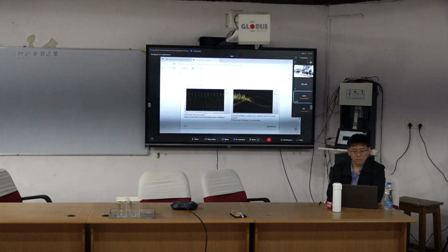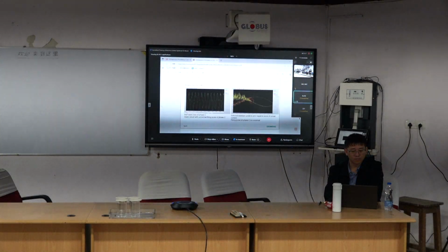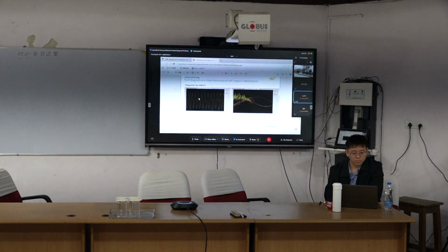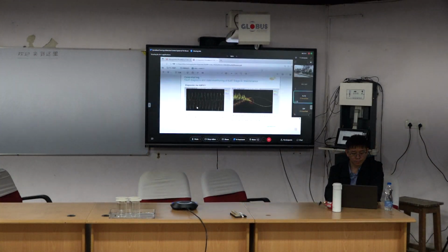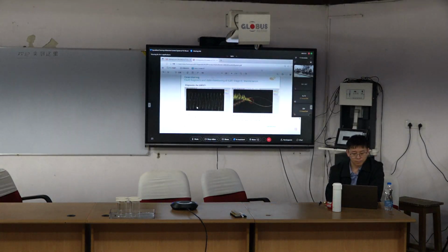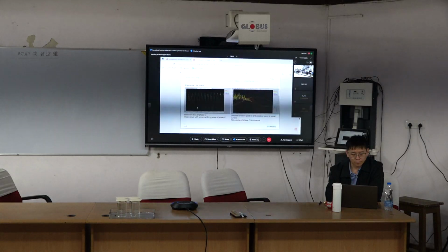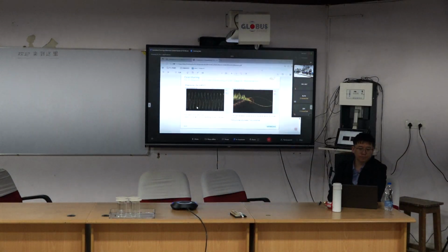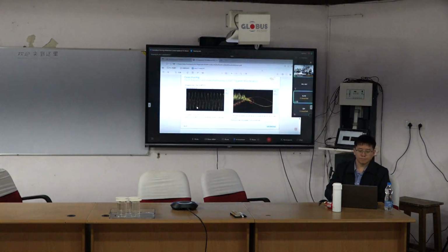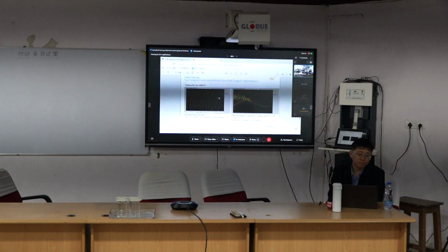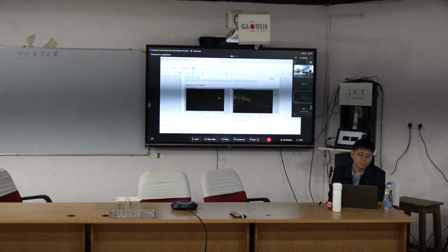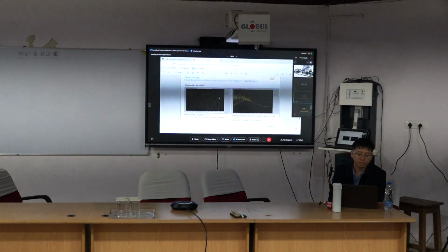This picture we also talked about. You can use the starter to choose the CT feedback, the actual current, to check maybe the IGBT or CT fault. This picture we just discussed.